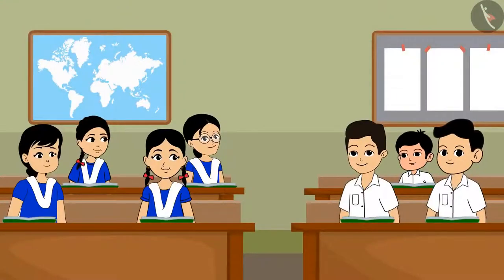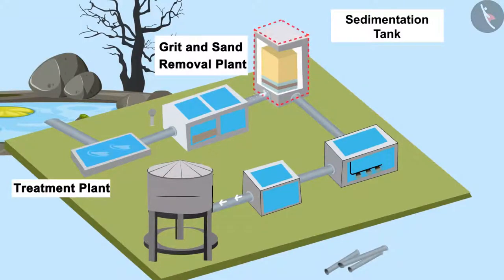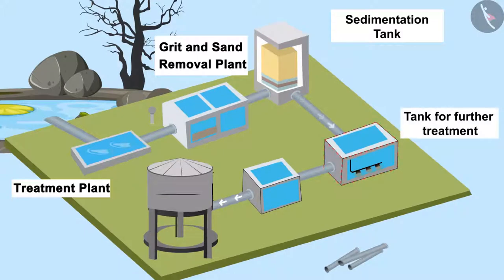It is such a big process. After this, the contaminated water is kept in a large tank for sedimentation. The contaminated water is left stagnant in a large tank about 5 meters deep. Heavy particles present in the contaminated water settle down and relatively clean water at the top is taken for further treatment. The contaminated water in this tank is kept for at least 2 to 6 hours. Oil, fat and grease are extracted by the process of flotation. The primary step of treatment is over.